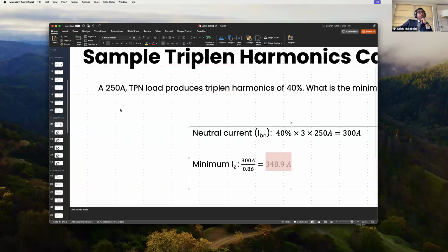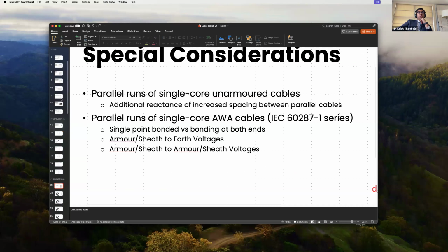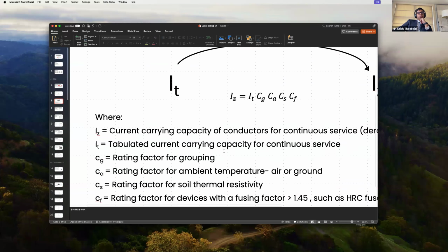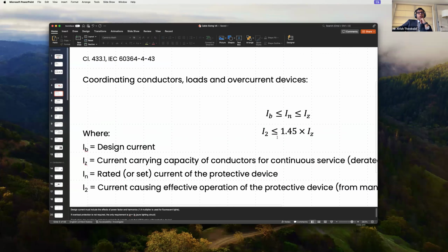The factors are applied for harmonics. So IB is basically the current after harmonics have been considered. This is either the line conductor current or the neutral conductor current as decided, which affects the size of the protective device.